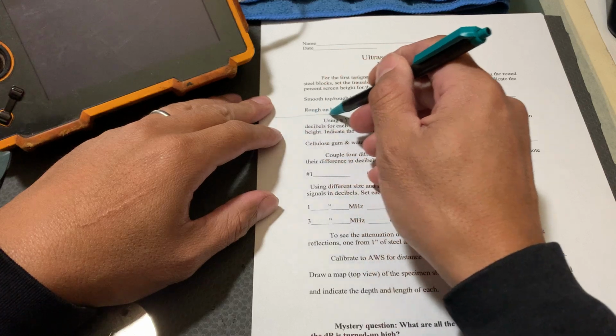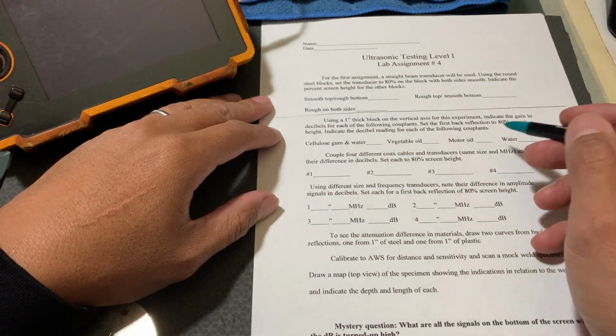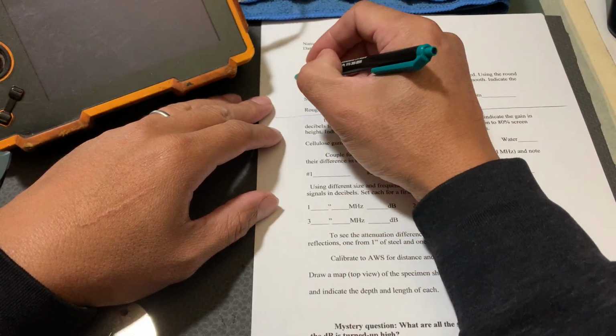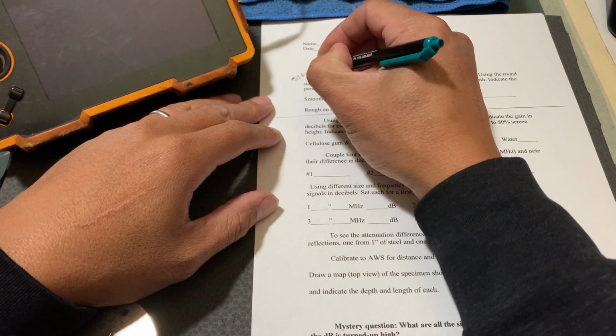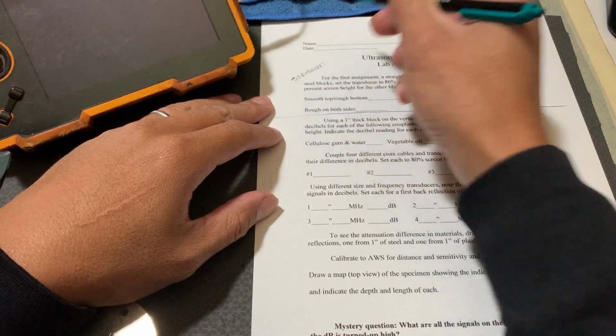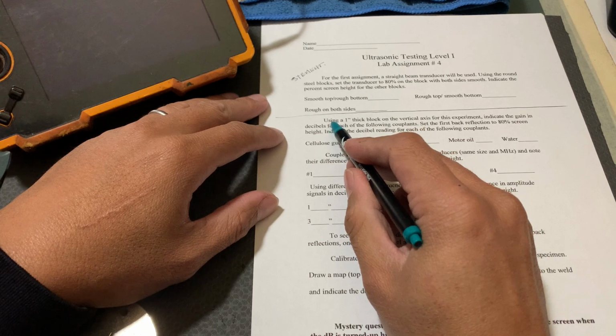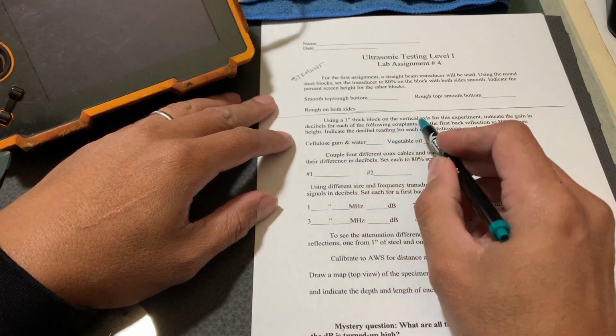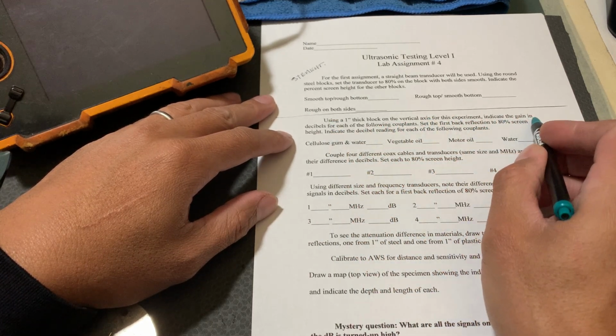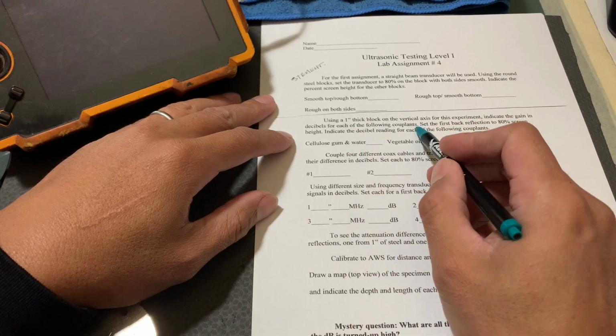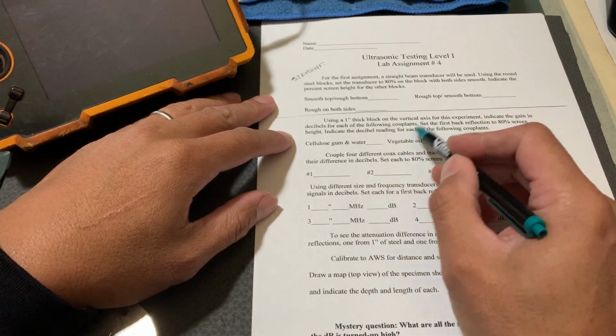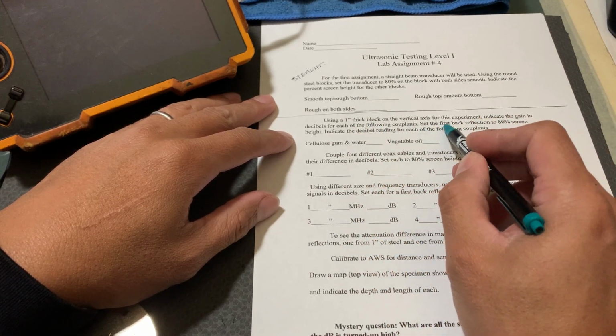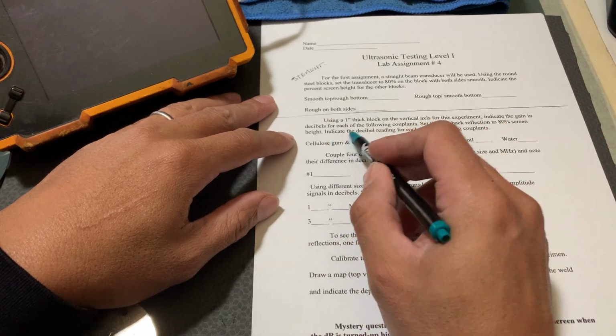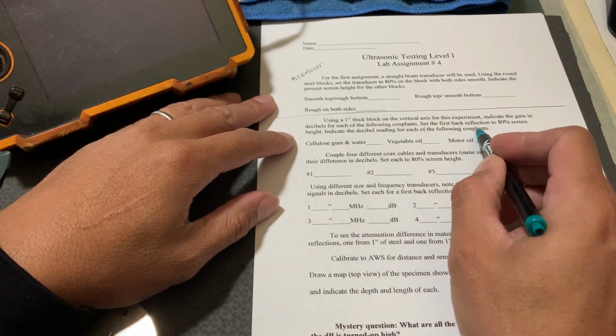So this is one part of the lab there. Just going to put a line through it. Of course, this is straight beam. Second assignment on this one is using a 1-inch block on the vertical axis for this experiment. Indicate gain for each decibel of the following couplants. So we're going to be messing with a few different couplants on this one. Set the first back reflection at 80% screen height. Indicate the decibel reading for each of the following couplants.